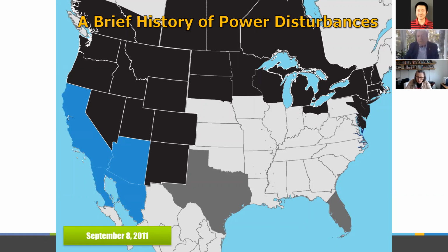September 8th of 2011, two electricians were switching out a capacitor bank over on the 500 system near Palo Verde. At this time, unfortunately, California ISO did not have visibility of the system where the problem precipitated from. But the bottom line, the Imperial Irrigation District down at 69 overloaded. It took about 2 minutes for this to propagate, and there was time for operator intervention, but there wasn't enough data in the hands of the reliability coordinator to take that intervention.